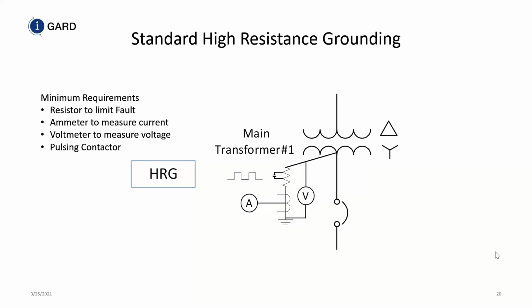So we have standard high resistance grounding systems. In standard high resistance grounding systems, at a minimum, you must have a resistor to limit the fault current. So this resistor over here. You may or may not have pulsing because unfortunately the NFPA 70E and Z462 just say use a high resistance grounding system, but they don't necessarily mean all the benefits of that. So we've had people who put in a high resistance grounding system, just put a straight 55 ohm resistor on the neutral to ground, put a CT on there and call it a resistance grounding system, slap on an arc flash mitigation technique on it and say they're happy and they're gone. But it doesn't do anything for them because it doesn't tell you where the fault is.